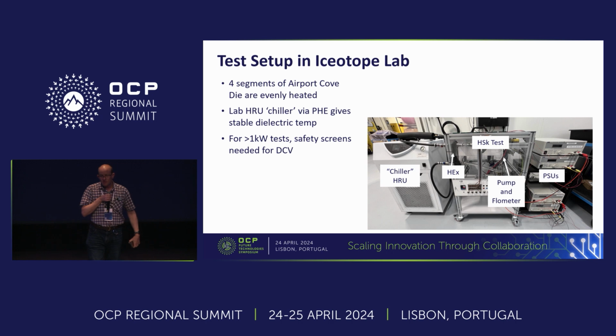A quick chat about the lab test stand. I won't dwell too much on it, but catch me later if you want more detail. Those familiar with the TTV know there are 4 component dies underneath, and that's why I've got a bank of 4 power supplies independently feeding each one. The heat sink you saw on the last slide is in the middle, the top chamber. Below that, we've got a circuit circulating the dielectric fluid, controlling the temperature, and accurately measuring the flow rate. The heat rejection is through the lab equipment you're seeing on the left.